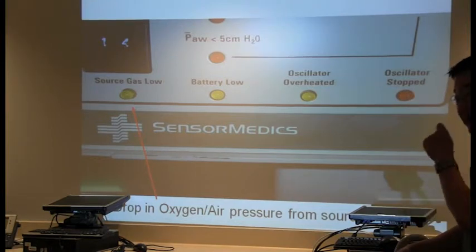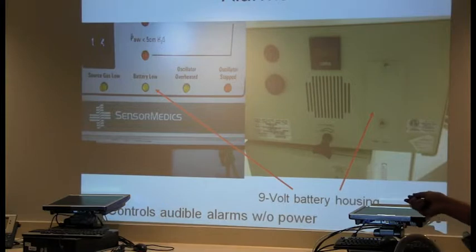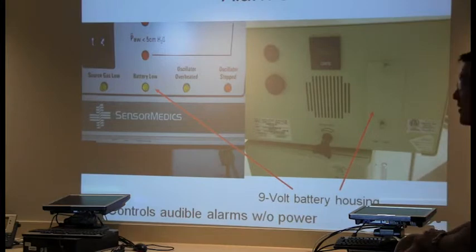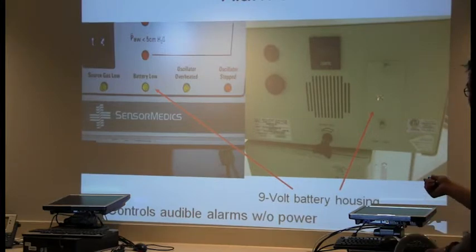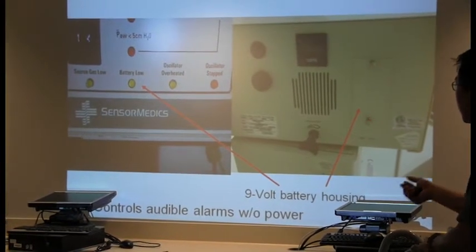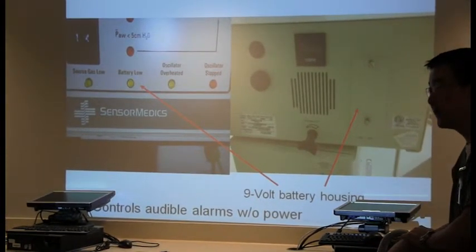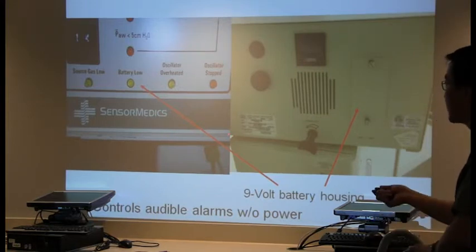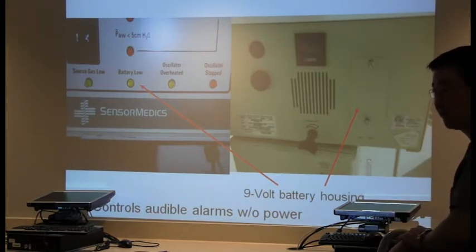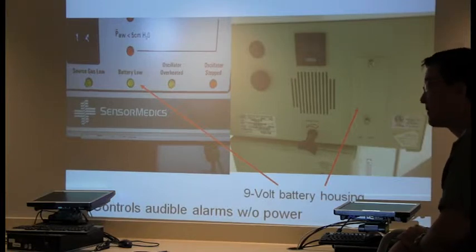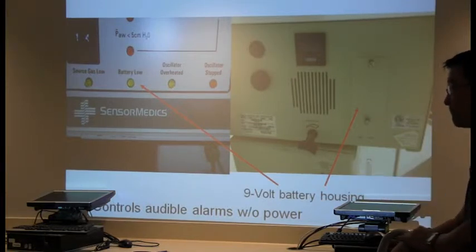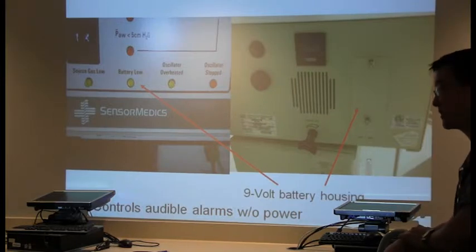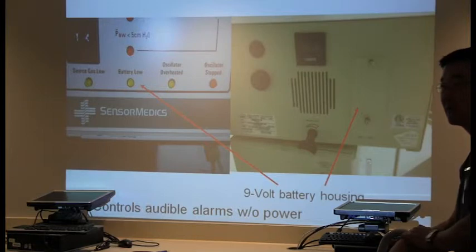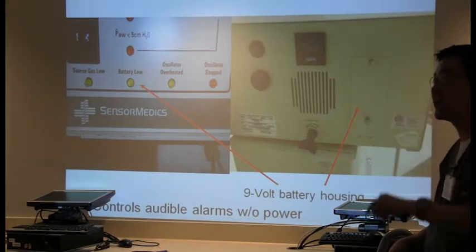Battery low. This little battery is probably the most important battery that you'll ever own or operate. In the back of the ventilator, in the housing, you unscrew two screws and there's a little 9-volt battery. That 9-volt battery controls your power disconnect alarm. What I mean by that is your ventilator is hooked up to the wall. Every Wednesday morning at 6 o'clock is the generator backup check, so the backup generator kicks in.